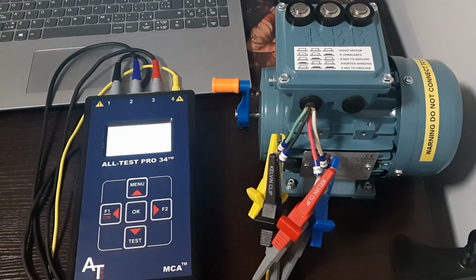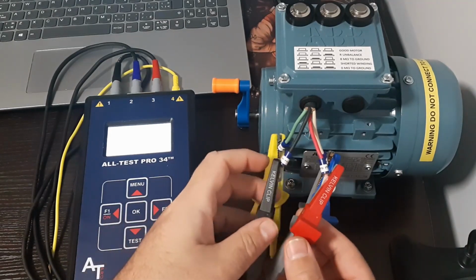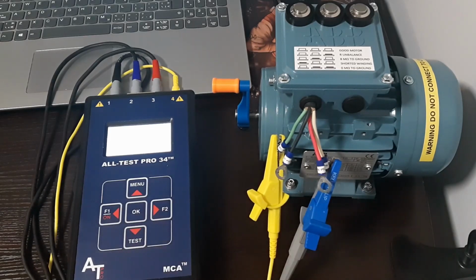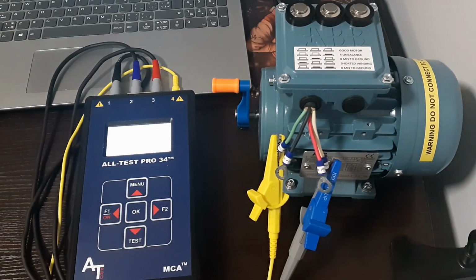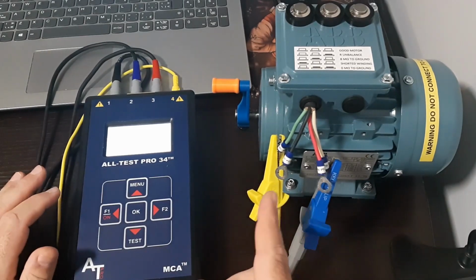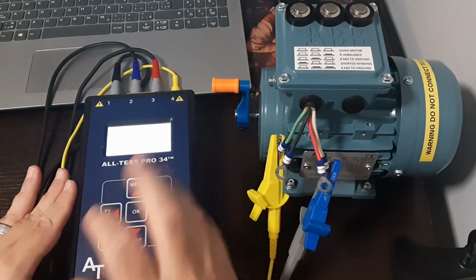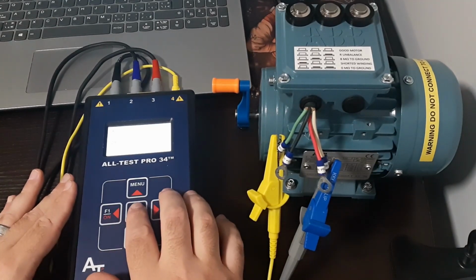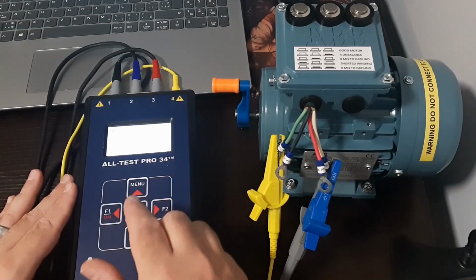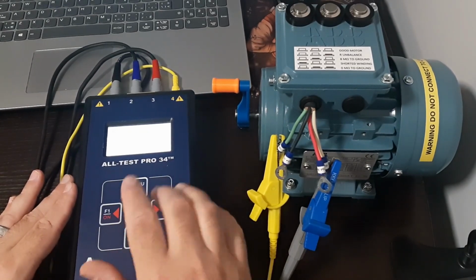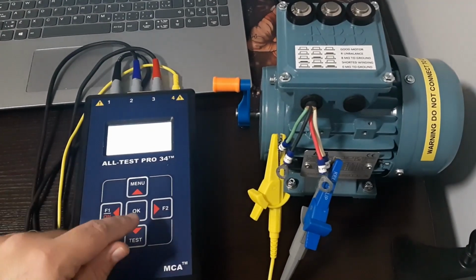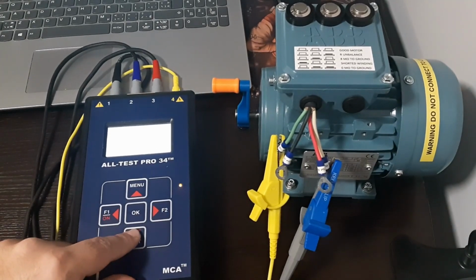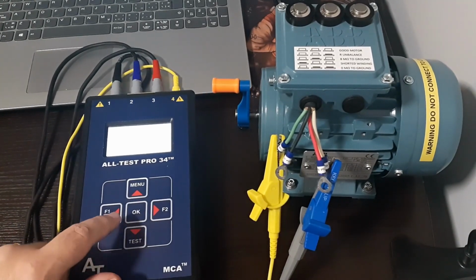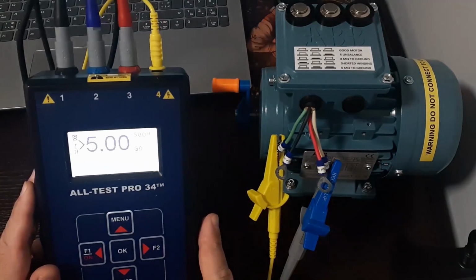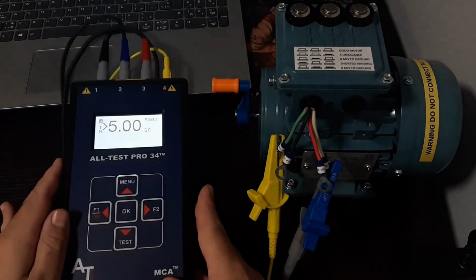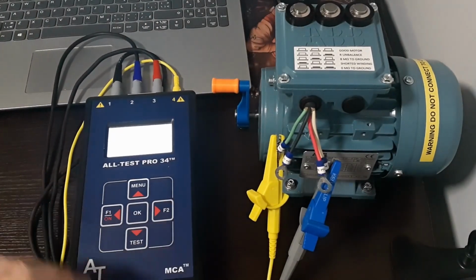So it immediately says, connect the blue clip and the yellow clip. Blue to number two and yellow to frame ground. These are already set there, so I'm just going to click OK. We're not going to do the CDF and cap test because we are connected directly to the motor, but we are going to do the insulation test, which is exactly what it was telling me the yellow and the blue were for. So I hold down the button until I get a solid number, which is that 5, and it has passed. So we're on to the next test.